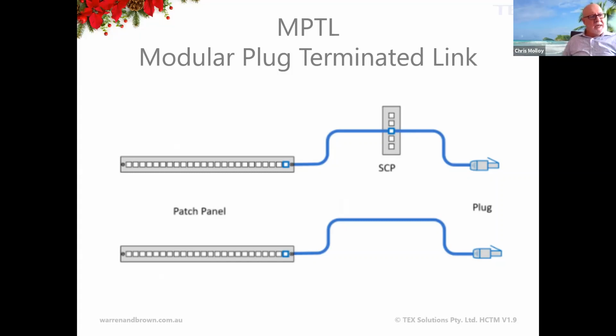A modular plug terminated link, as the name suggests, just means that we do what is shown in this slide. You can just put a plug on the end of the cable rather than terminating that cable into an outlet and then using a patch cord or fly lead to plug into the active device. It's specified in 11801-1.